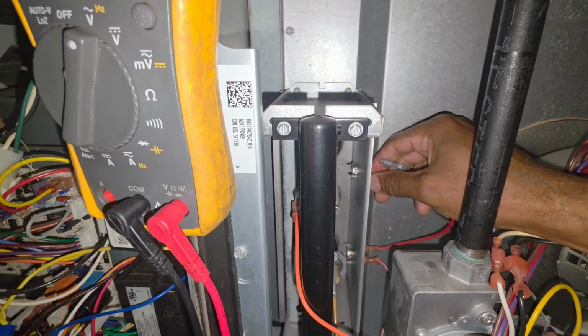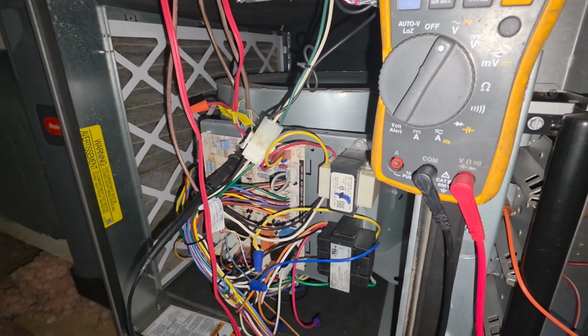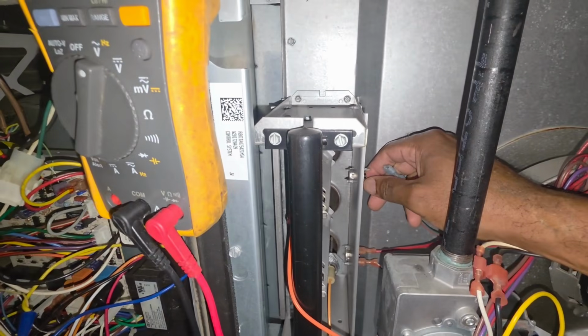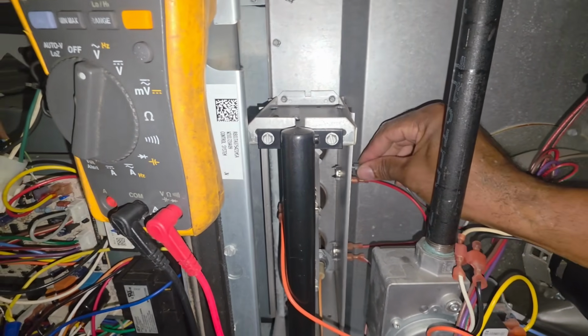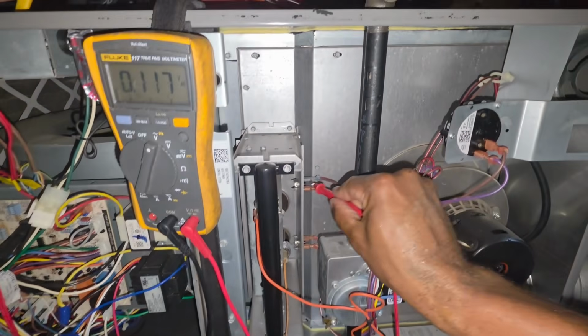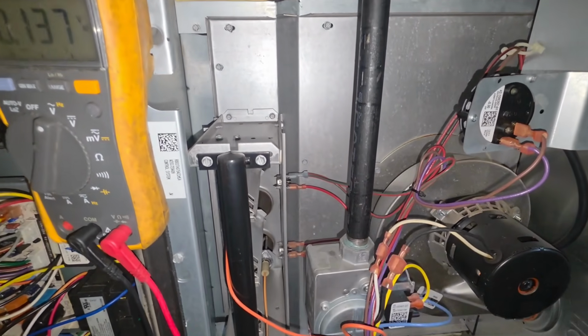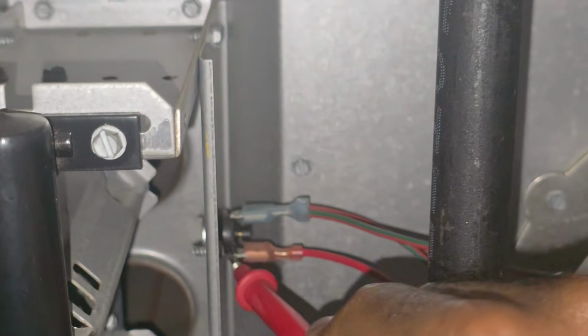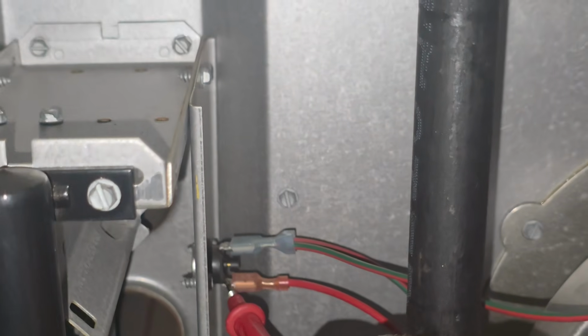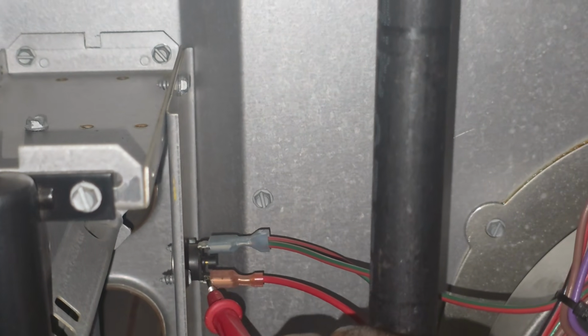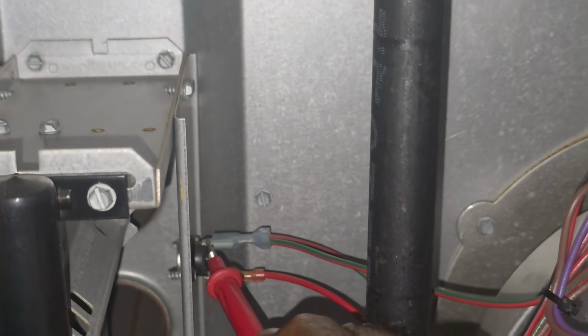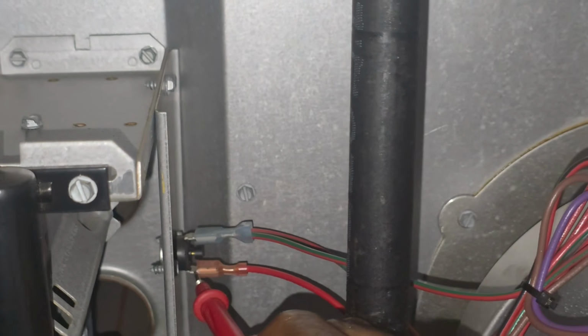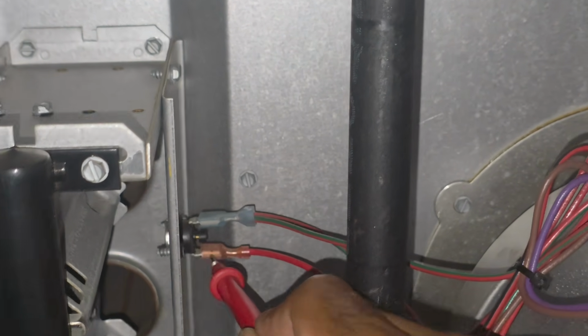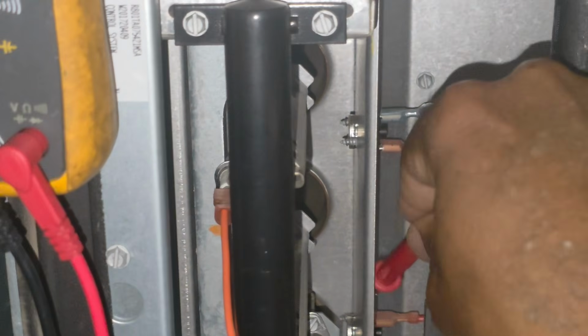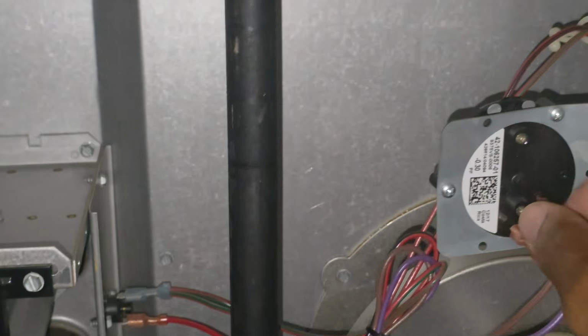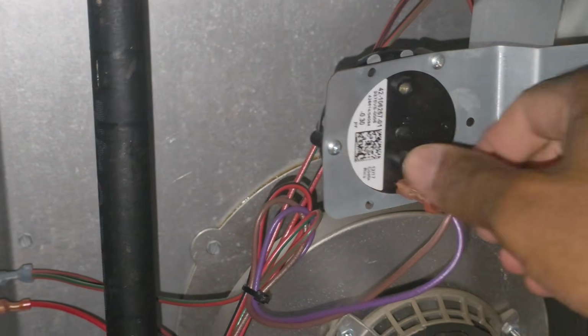That's what we're checking. And we got our pivot foot on the common, and we'll put one right here. You should get voltage. You go to the top, you should get voltage. If we go here, we got 24, but we go up here, we got 0. Same thing on all of them. Pretty much just 2 terminals. On your pressure switch, same thing.